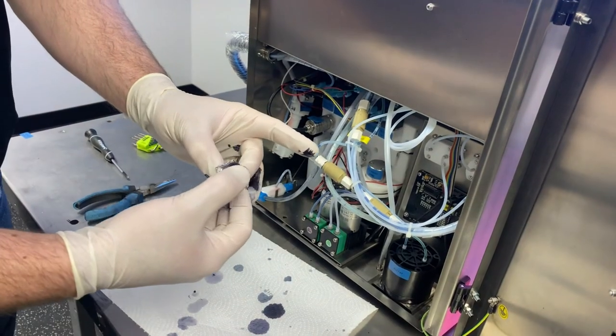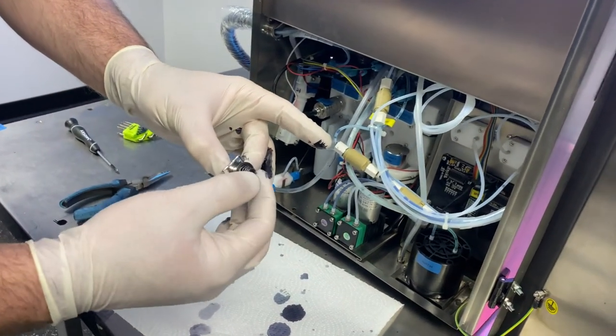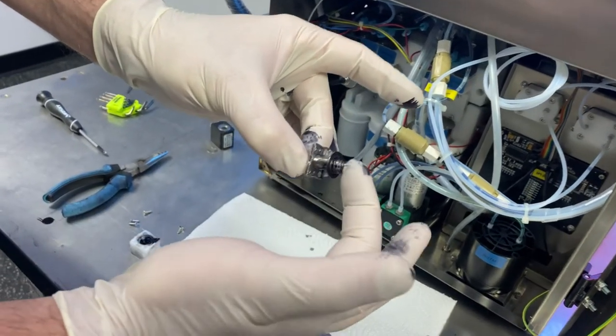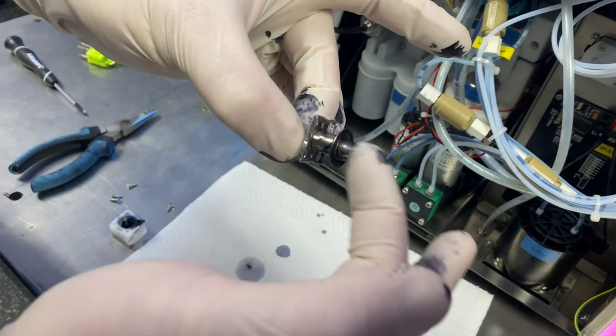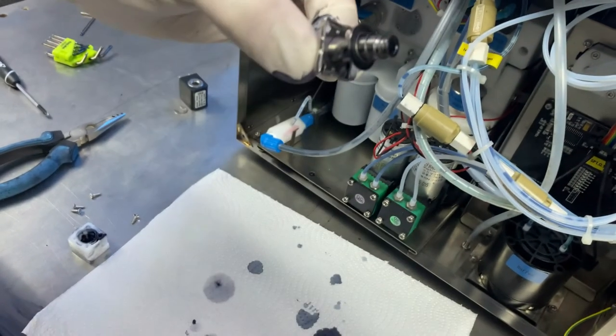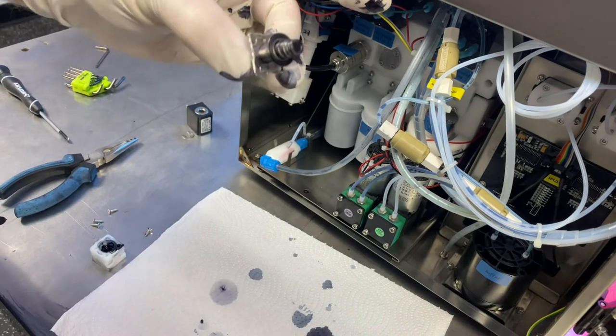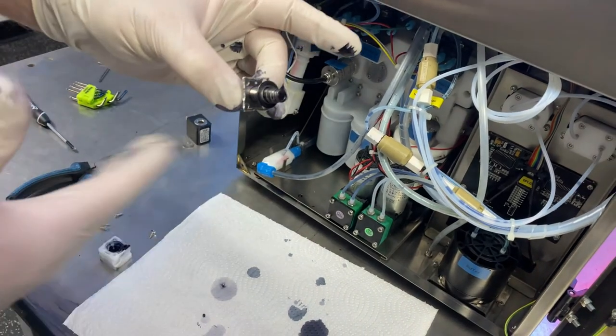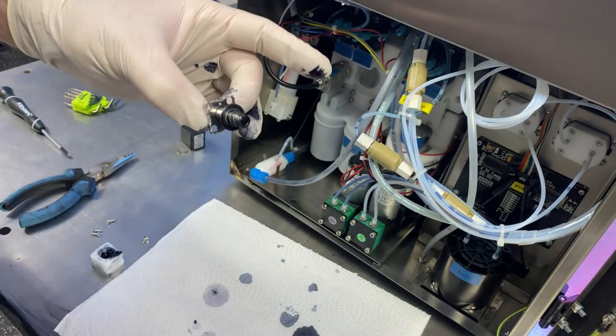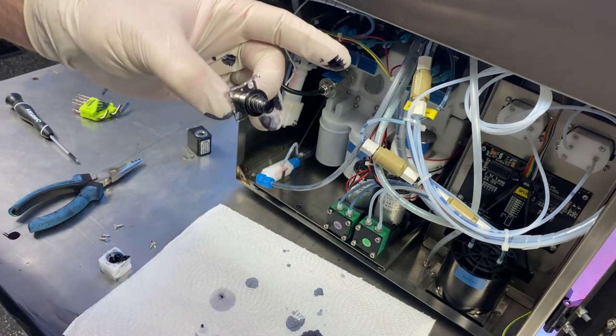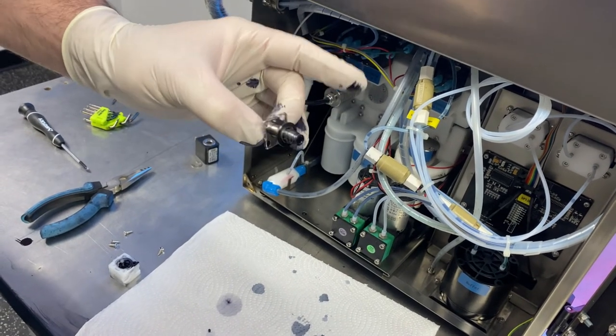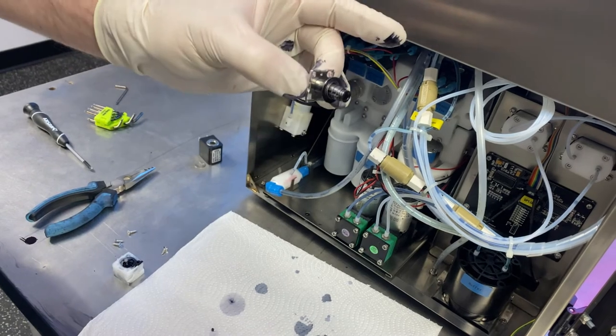Okay, so once you've got this cleaned up, that spring should be moving freely, that plunger should be moving freely - that's what we want to see. So now we're going to reassemble the entire valve or plunger assembly. We'll slide this back into the solenoid, then reconnect our hydraulic line and wires, and put this back on the manifold.